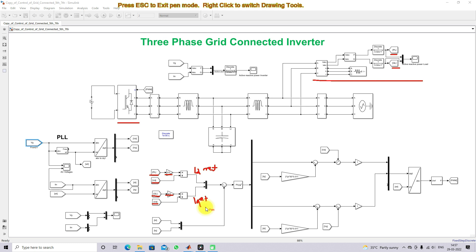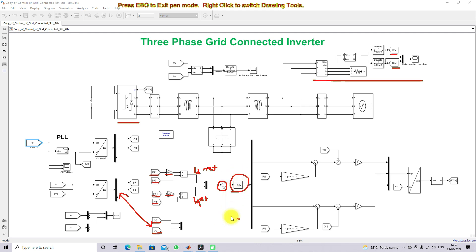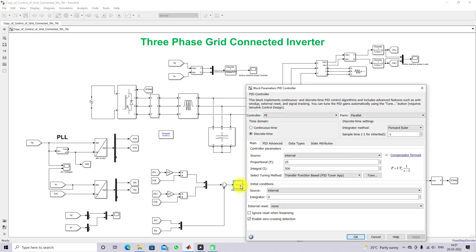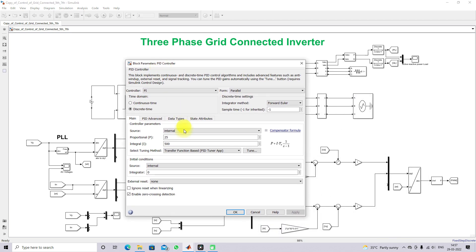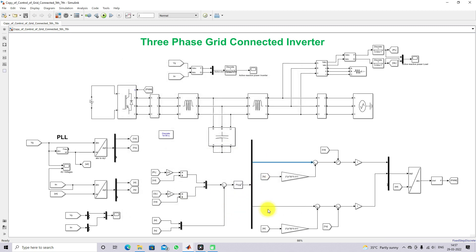Similarly, the IQ reference is derived from the reactive power load. The ID and IQ of the inverter are compared with ID reference and IQ reference, then processed via a PI controller. The PI controller generates the control signal; the PI controller values are 25 and 500.